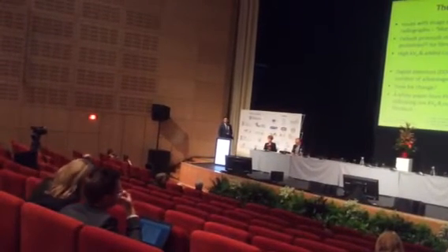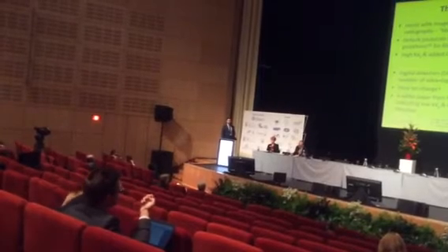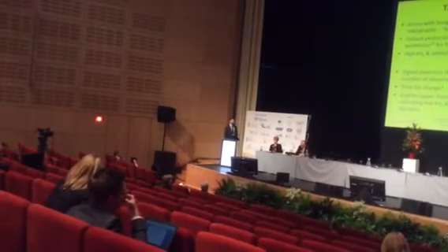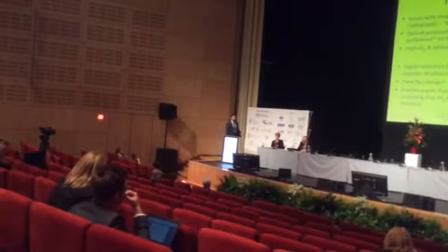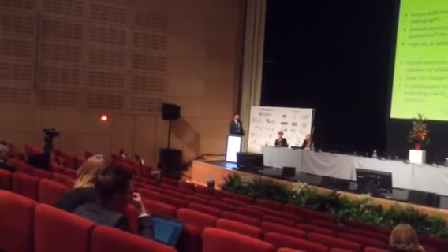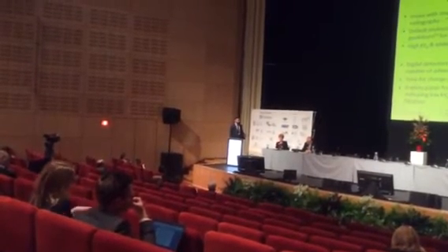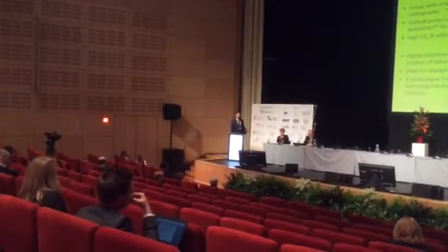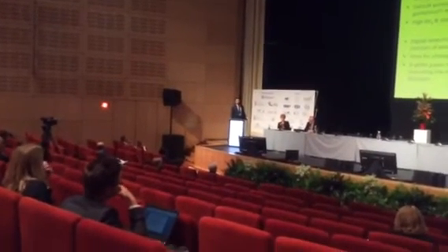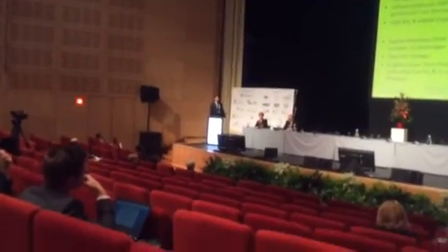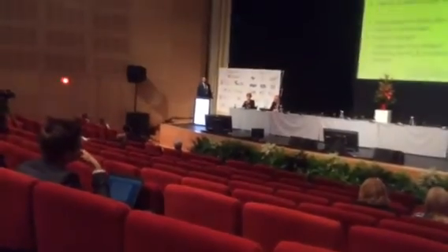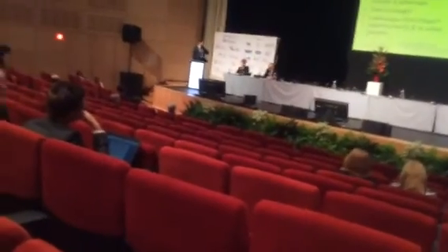However, digital detectors have numerous advantages over film screen. Firstly, film screen is limited to the fixed detector dose in order to display the optimum contrast, whereas digital has a wide dynamic range, meaning that the contrast can be displayed no matter what dose is absorbed in the detector. The only limit there is in terms of dose reduction is that as the dose is reduced, the noise starts to increase up until a point where the system moves away from being quantum noise limited and the electronic noise begins to dominate the signal.